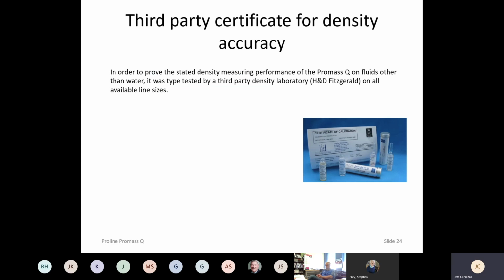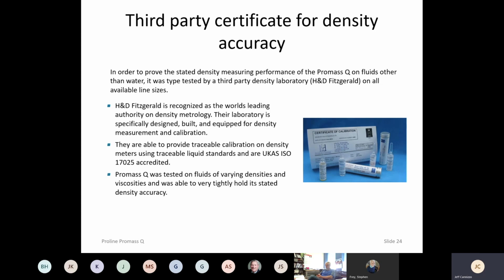Again, Endress+Hauser being a conservative company, most of our statements that we make are proven by a third party. So in this case, H&D Fitzgerald verified everything that we're telling you in the specification. They tested the Promass Q on fluids of varying densities and viscosities, and it was able to hold its stated accuracy. So in all cases, when you buy a flow meter from Endress+Hauser, you're going to get a flow accuracy statement or a flow accuracy chart and a density accuracy chart on a Coriolis meter.